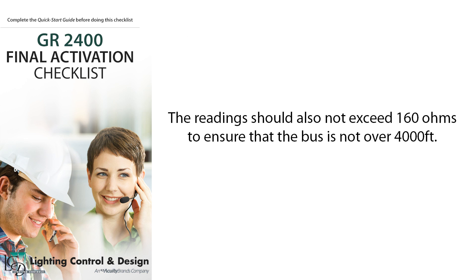The readings should also not exceed 160 ohms, to ensure that the bus is not over 4,000 feet. If the test readings fail, please go back and check the system for damaged cables or bad crimps.